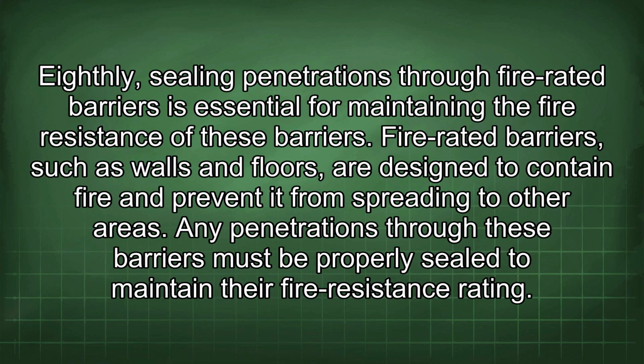Eighthly, sealing penetrations through fire-rated barriers is essential for maintaining the fire resistance of these barriers. Fire-rated barriers, such as walls and floors, are designed to contain fire and prevent it from spreading to other areas. Any penetrations through these barriers must be properly sealed to maintain their fire resistance rating.